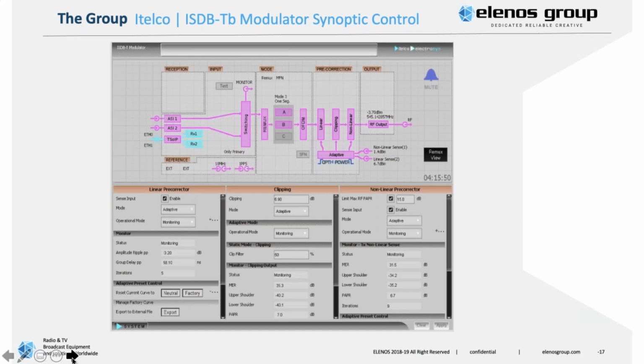Instead, in case of multiple amplifiers, we have a unit that is named CCU, the transmitter control and supervising unit, and all the information from the power supply, from the power amplifier modules and exciter are addressed to this control unit that has the web browser connection built in, and all the information are addressed through a CAN bus port. So basically this unit is capable to control the entire transmitter.